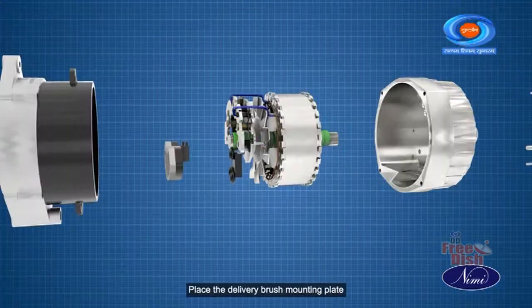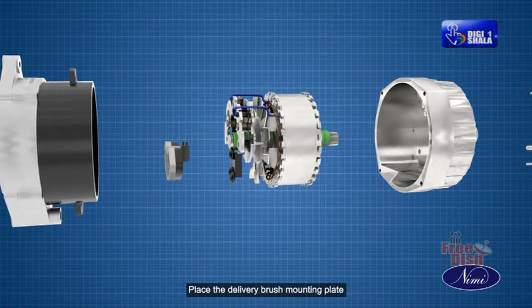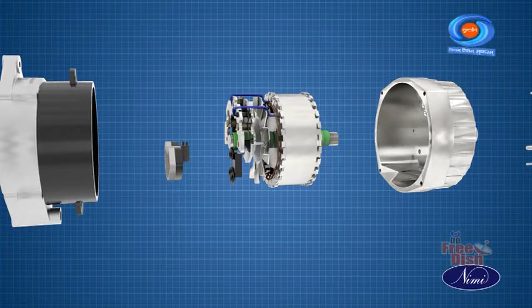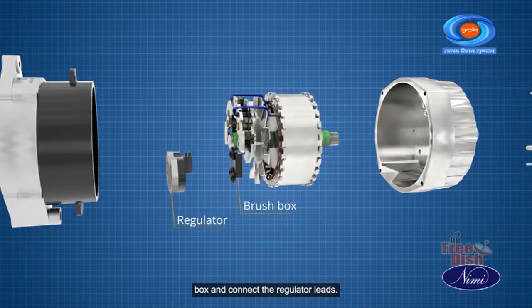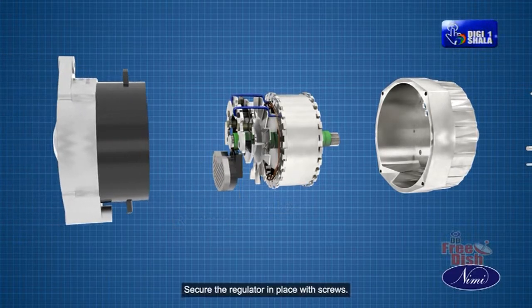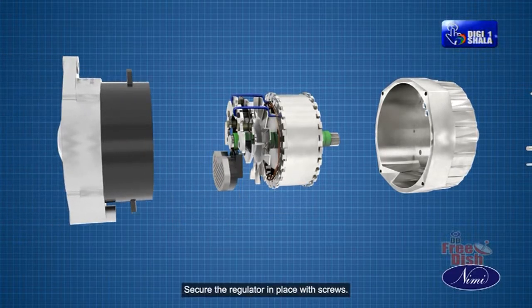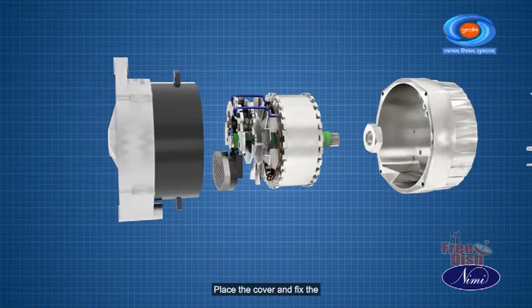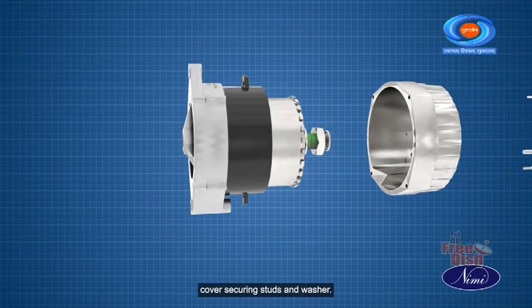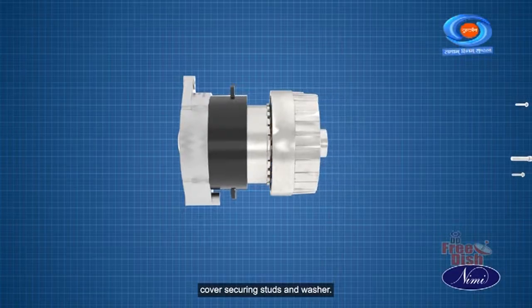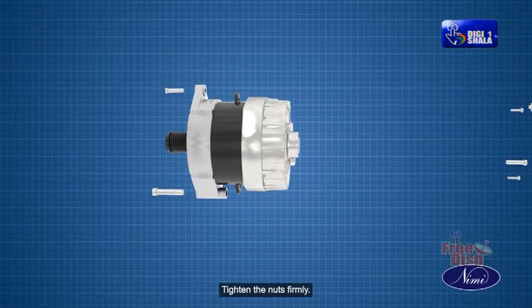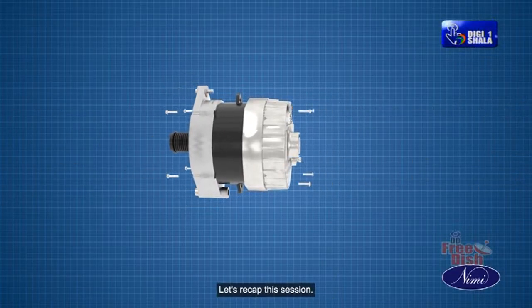Place the delivery brush mounting plate in position and secure it with screws. Place the regulator on the brush box and connect the regulator leads. Secure the regulator in place with screws. Place the cover and fix the cover securing studs and washer. Tighten the nuts firmly.